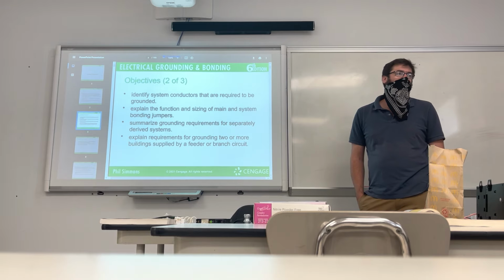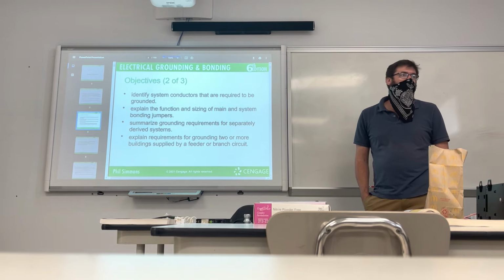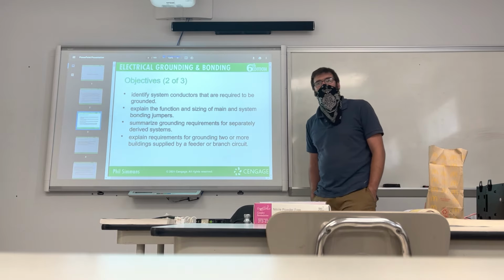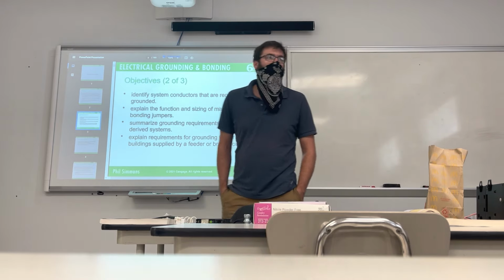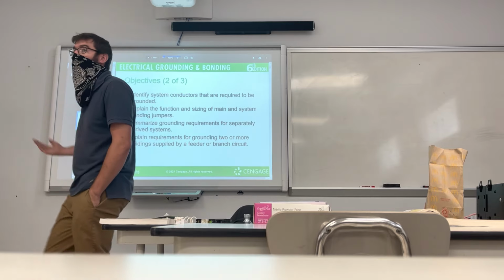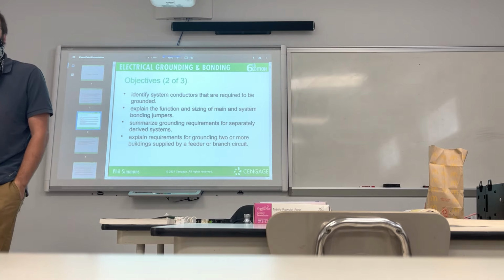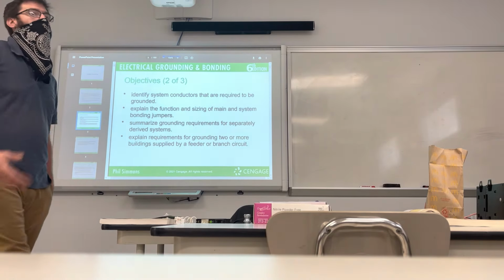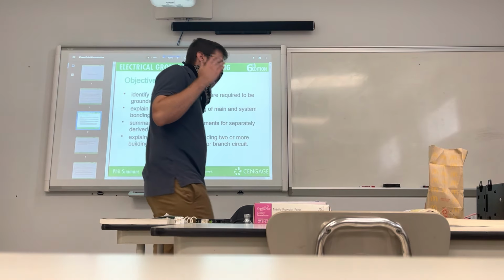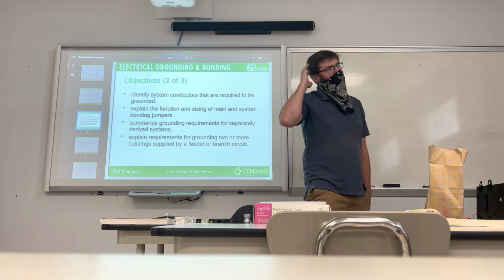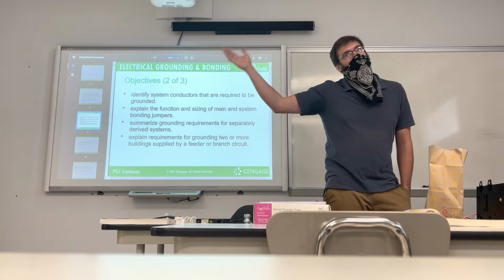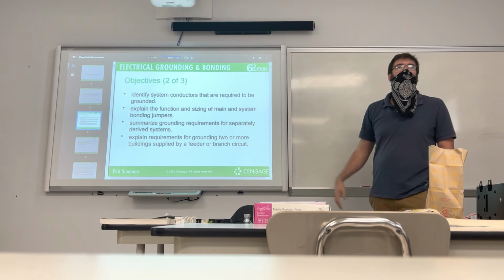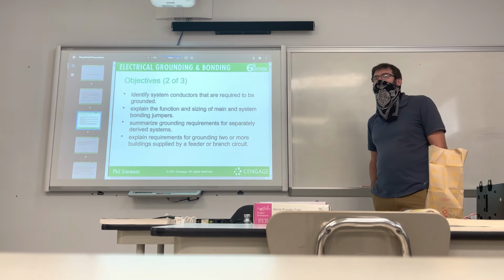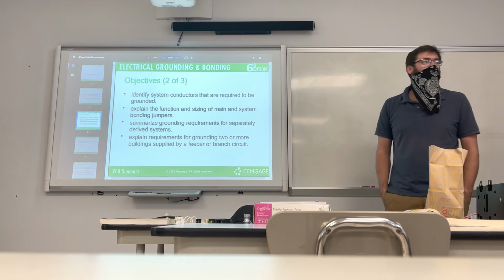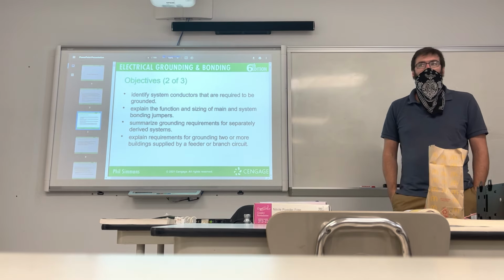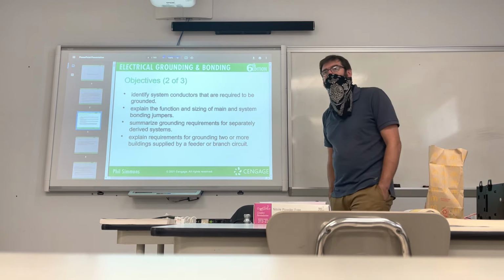And if it's in the main panel box, it should be on a ground bar. Yep. And that's a guarantee. You know what I mean? When it comes into your house, there's definitely gonna be a main panel box, right? You're not gonna come into your house in a sub panel, right? So it's gonna be bonded there. But where's another place that has to be bonded that we see all the time, but we're not actively thinking about? It shows it in every single slide, but I just want to make sure we're all on the same page when it comes to this. Where's another place that neutral wire is grounded?